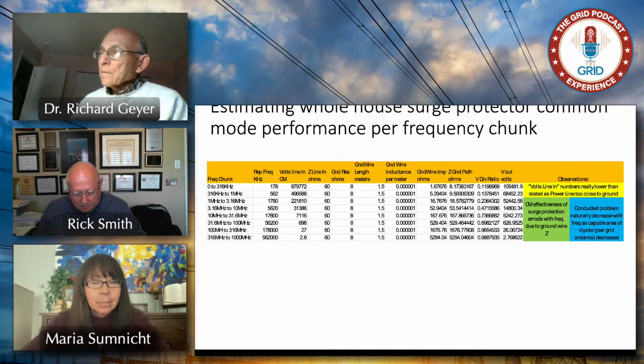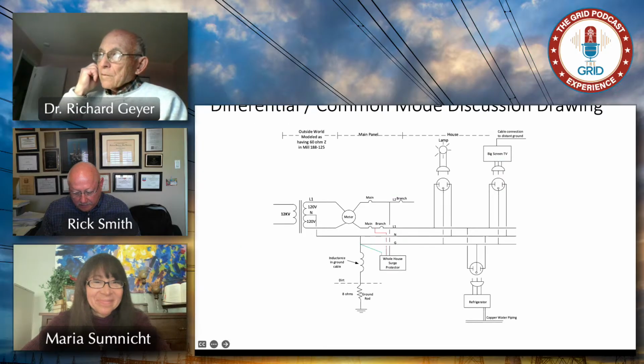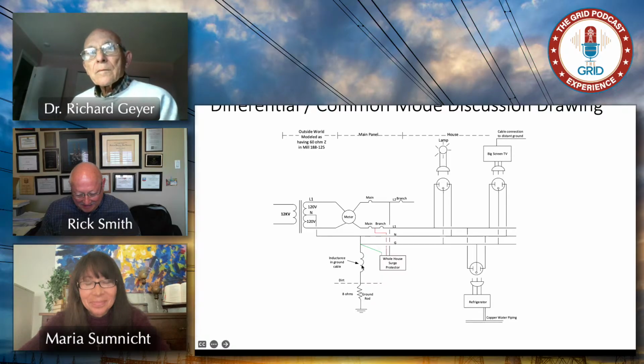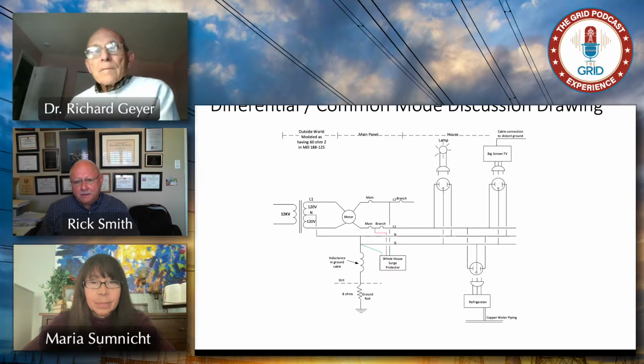Actually, I need to go back to the diagram. In the analysis, we're going to go back to the MIL 188 standard and assume the outside world can be represented by a very simple 60 ohm resistor in terms of its source impedance. So what you end up with is a simple voltage divider circuit: a 60 ohm impedance in series with the inductance of the ground wire leading from the surge protector to ground, and then the resistance of the ground rod itself.